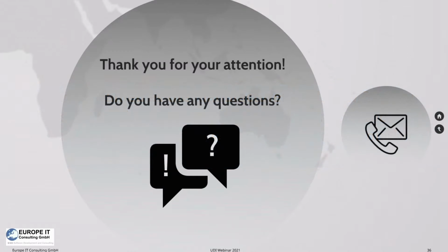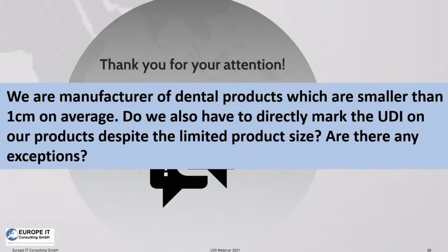And the last question is, we are manufacturers of dental products which are smaller than 1 cm on average. Do we also have to directly mark the UDI on our products despite the limited product size? Are there any exceptions? Generally, all reusable medical devices must be marked directly.